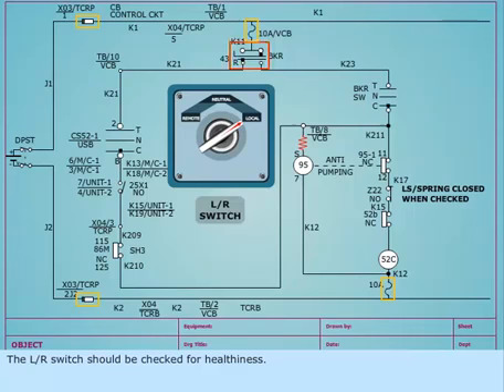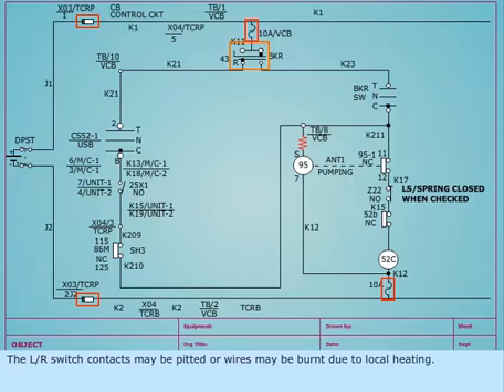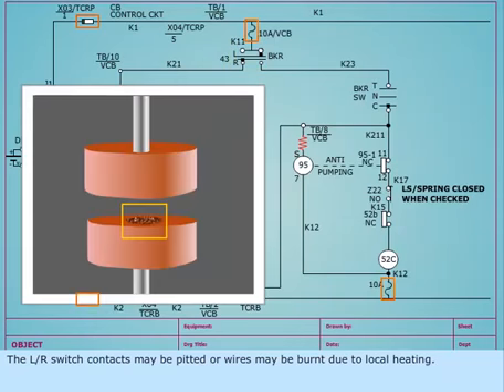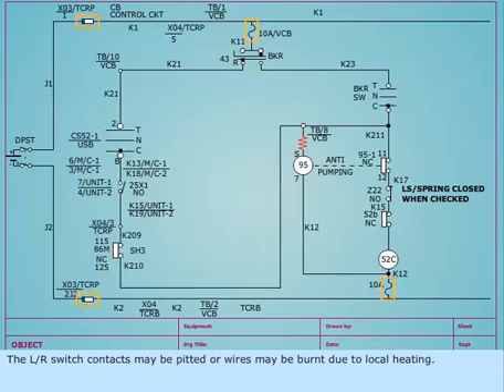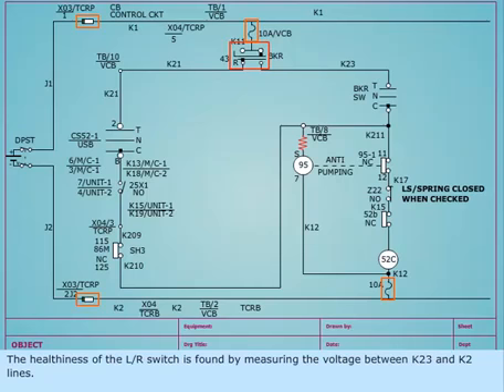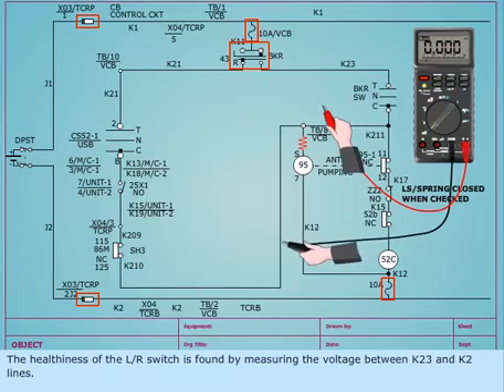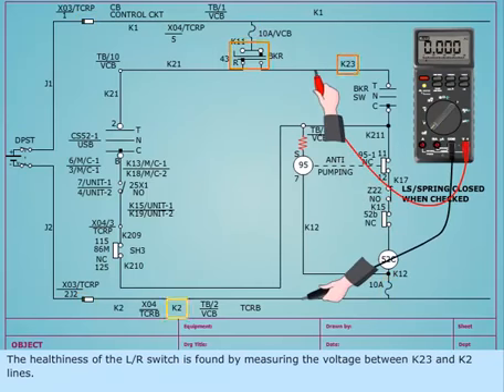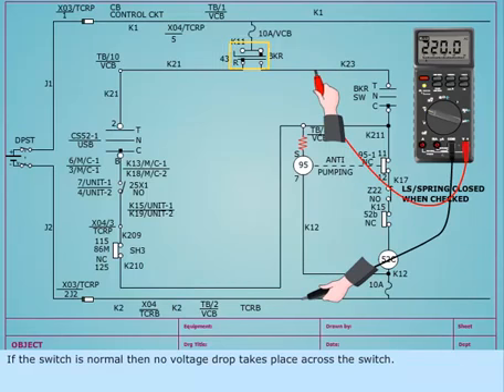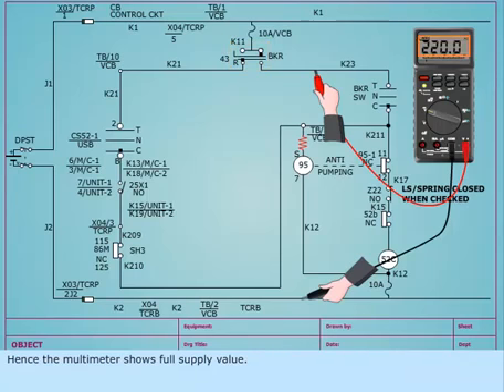The L/R switch should be checked for healthiness. The L/R switch contacts may be pitted or wires may be burned due to local heating. The healthiness of the L/R switch is found by measuring the voltage between K23 and K2 lines. If the switch is normal, then no voltage drop takes place across the switch. Hence, the multimeter shows full supply value.